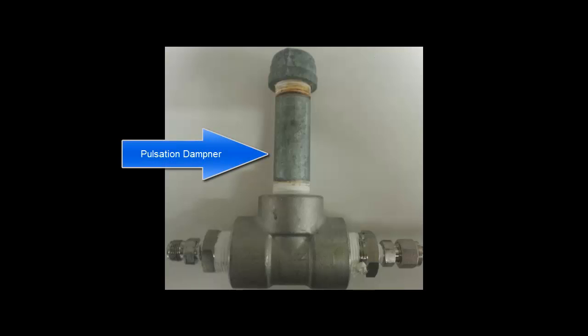The pulsation dampener is located downstream of the PD meter and upstream of the injection pump. It's used to protect the integrity of the measurement from the suction and discharge of the pump itself.